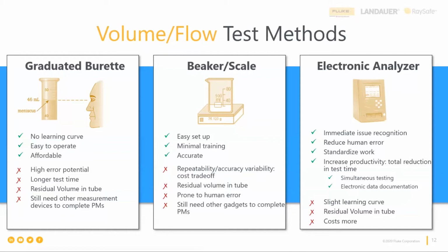The weakness would be that it is not automated. So it requires the operator to be dedicated to testing one infusion channel at a time, or to be highly skilled to use multiple burettes and a stopwatch with sufficient splits to capture the infusion beginning and end for each infusion channel, which is highly difficult. There is a relatively high error potential because of the improper viewing of the meniscus. You can see in the picture on the left how the burette has to be positioned straight from the eyes of the operator to ensure the correct reading.